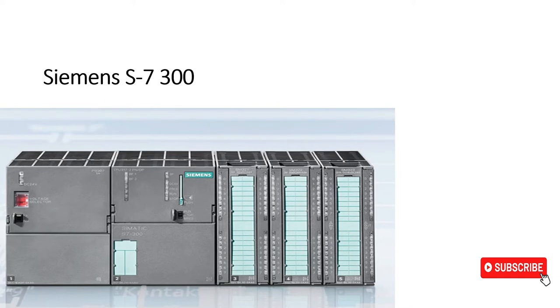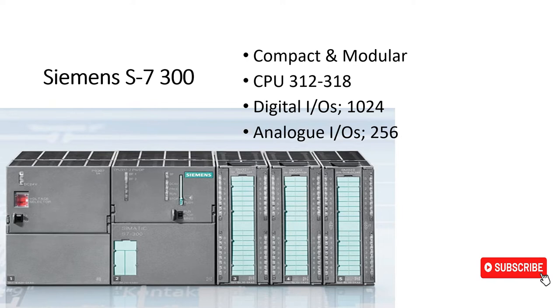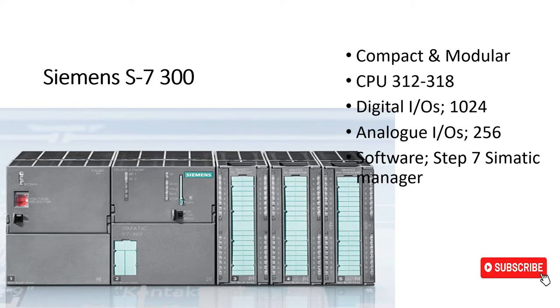Let's start by going through an overview of the Siemens S7-300 PLC. It is a medium-level PLC which is compact and also modular. Its CPU versions run from 312 to 318, and it can support up to 1024 digital inputs and outputs and up to 256 analog inputs and outputs. The software used to program it is Step 7 SIMATIC Manager.